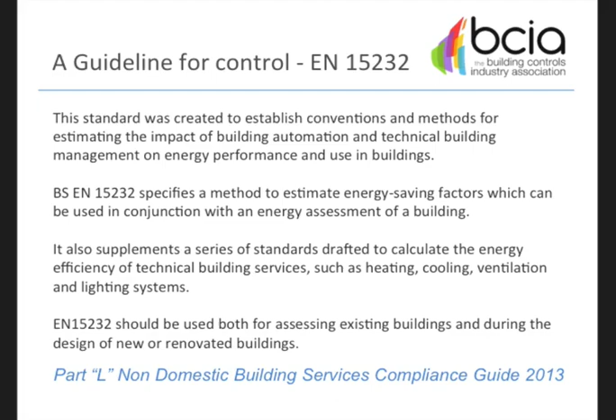How does it work? It's an EPC at the end of the day - a high-end BACS would get you an A-class building, a low-end BACS would give you a C, and a non-efficient BACS or building automation control system would get you a D. EN 15232 is referenced at a level C, or a hinge point, for all buildings.